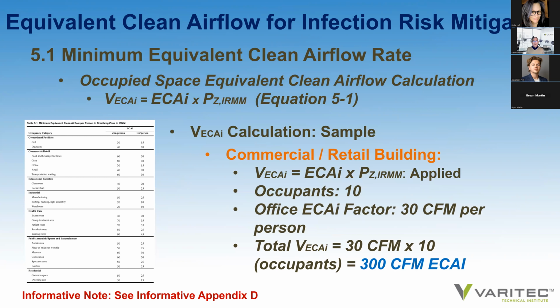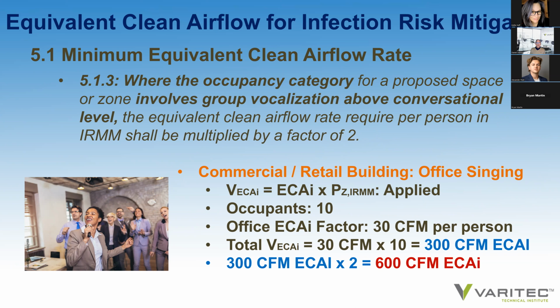So to give you an example, if we look at an office space that has an occupancy of 10, maybe it's a conference room, to calculate the amount of ECAi air, or equivalent clean air, that is to be supplied to the space, take the 30 CFM per occupant as defined by the commercial retail CFM per person guideline, multiply it by its occupants, and you'll see that you would need 300 CFM of equivalent clean air at the breathing zone of those occupants when a building goes into infection risk management mode. Under paragraph 5.1.3, it also offers this, that if a group of occupants are involved in vocalization above conversational level, then the factor of airflow is to be doubled. So if for some reason there's karaoke going on in the conference room, then the airflow rates would be doubled up to 600 CFM.